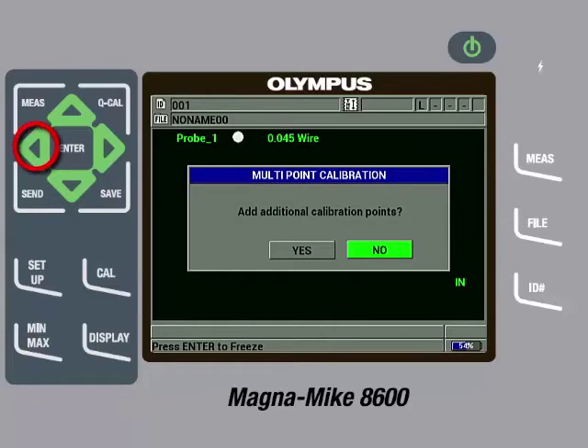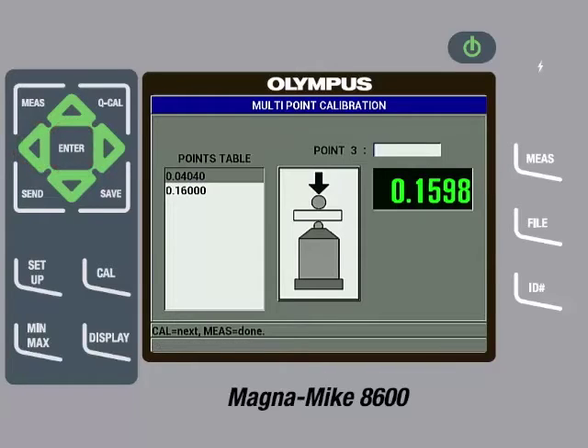Therefore, we will press the left arrow key to highlight yes, and then press the Enter key. The gauge now shows the thin and thick calibration points we have already entered, and it is asking for the next calibration point. At this point, we can add in the other reference standards from the calibration kit that we have not yet entered. We can remove the thick shim fixture.